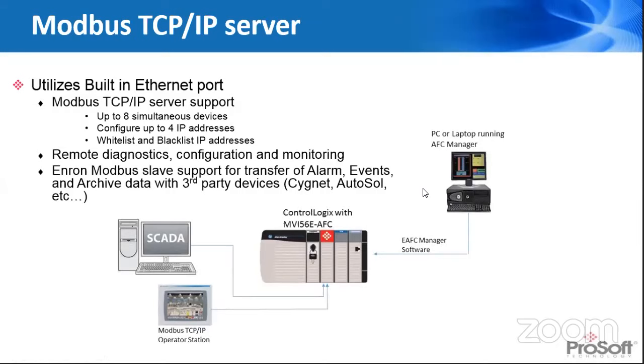On the SCADA side, I mentioned a lot of the flow computers are utilizing Modbus TCP/IP, and so we were able to add support for Enron Modbus, which is basically a file transfer for historical data that a lot of flow computers use. That allows us to tie in with systems such as Cygnet and AutoSol to pull that measurement data. A lot of times they'll utilize those systems to look for any abnormalities in the measurement related data, and make corrections if something like a transmitter failed during that time. So they're able to get all that historical data and still perform whatever functions they need from a measurement perspective.